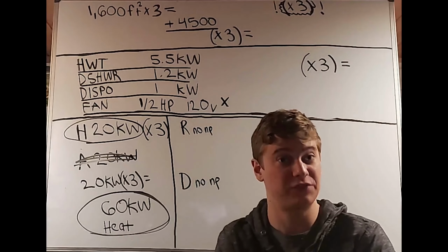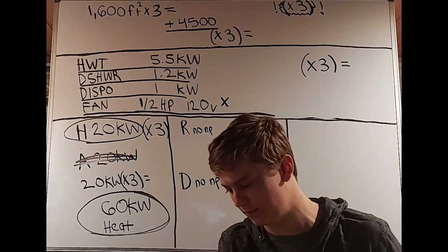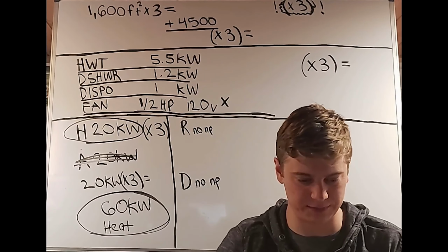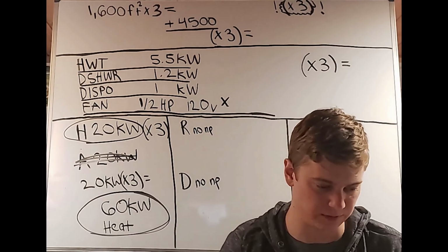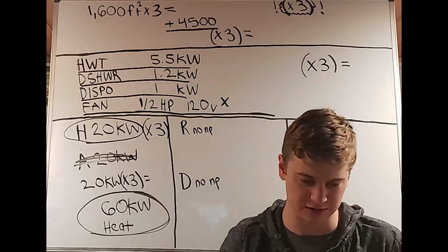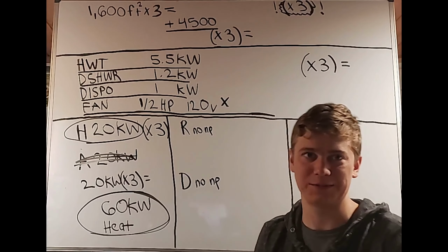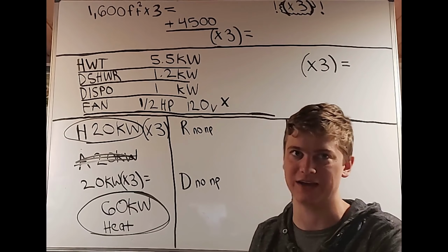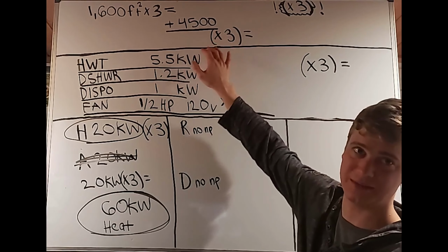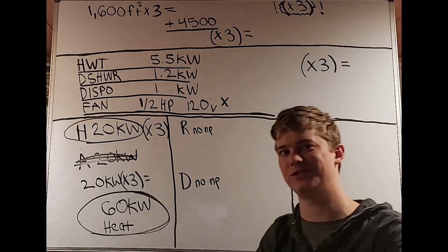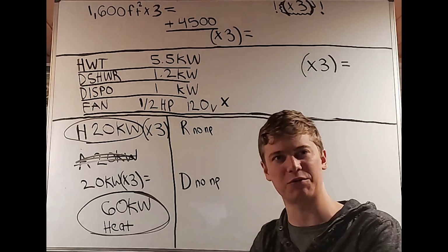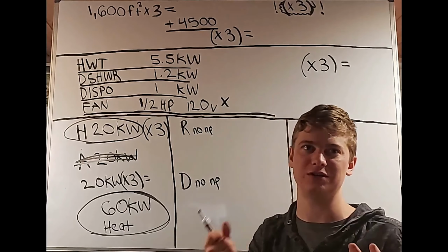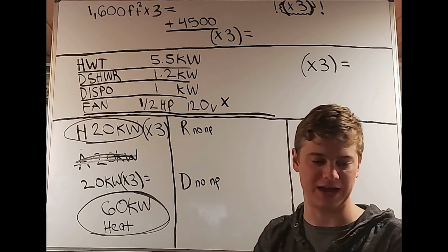So I discussed briefly what to do in the summary, but now I'm actually going to go through with it a little more in depth here. Okay, so when we don't have the nameplate rating of the range, we're going to go into table 220.55 and look at column C. The only thing here is that for the optional method duplex, we're not going to think about the number of appliances that we have, since we're multiplying everything by 3. It's kind of weird how we're multiplying everything by 3 and using the multifamily table.